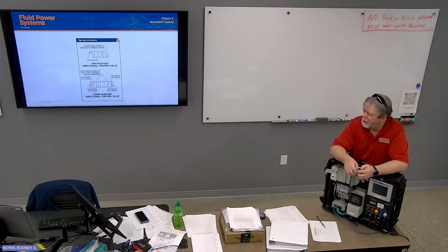Spring actuators, when one spring is present, the one on the right hand side, so spring offset. So by our naming convention, what type of valve is that? Andy? It's spring loaded, 2 position, 4 port. Incorrect. Okay, that's 4 ports. So port / position. Okay, 4-2. 4-2, spring loaded. I'm not talking about the top one. 4-2, port position, or 4-port 2 position.